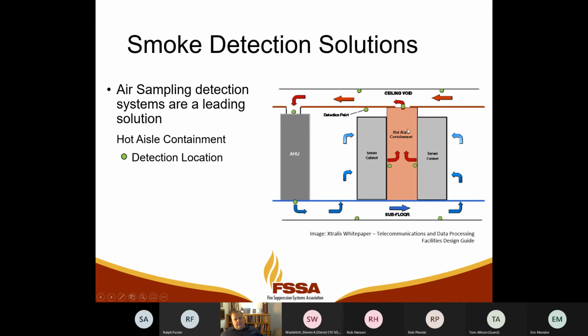The guidance for VESDA is a great product to use. Air sampling smoke detection, specifically VESDA. And what we do is we put a pipe right down the middle of the contained aisleway, and we put a sampling hole in it every 6 feet, and that meets it. We've had successful smoke captures under thermal conditions. That's a great way to do it, and that's what's recommended by Xtralis for their VESDA product.